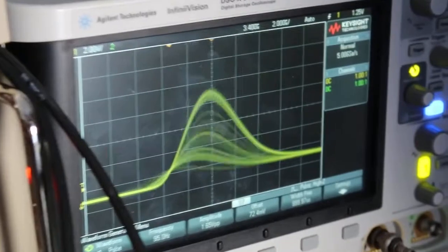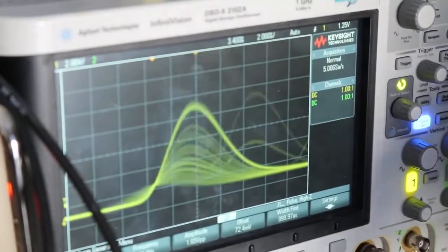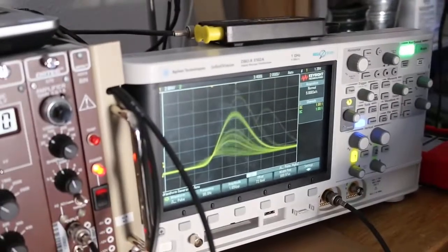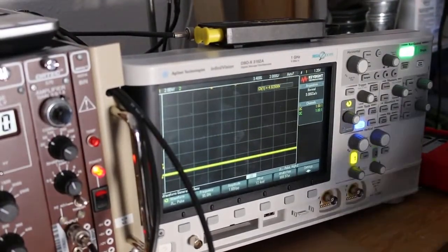So basically it's a voltage between 0 and 10 volts that's going to come in, and this is what we have to wonder about. Okay, so to analyze this, I'm going to go down to the oscilloscope, where we have our gamma ray signal still coming in pretty strongly. I'm just going to disconnect it from this connector, take it off, and so there's no more gamma ray signal.